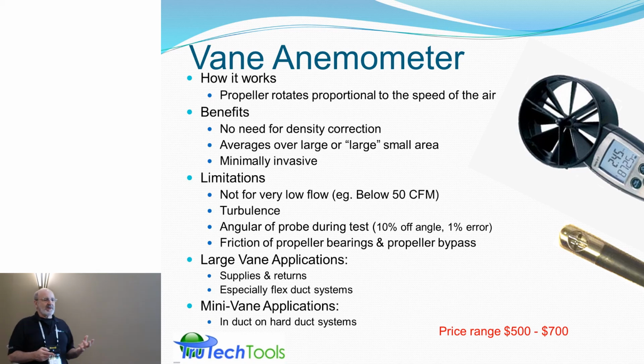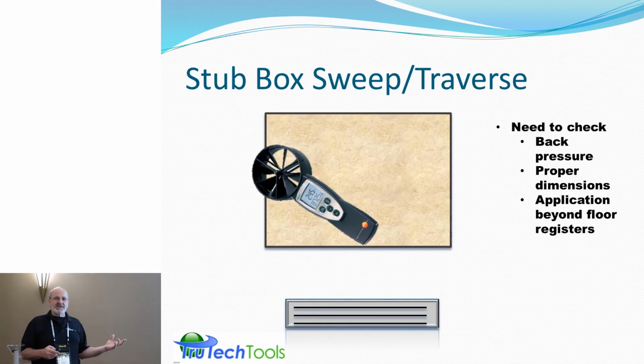One question: how do I calculate an open area when I don't know it? It's not available. And this was a suggestion given to me by a TSI engineer. He creates what he calls a stub box. Basically, it's field fabricated. They work really good on floor registers, but they don't work so great in wall or ceiling registers because you need to tape them up. But if you place a box around and sweep across the top area, that's a free area, okay?